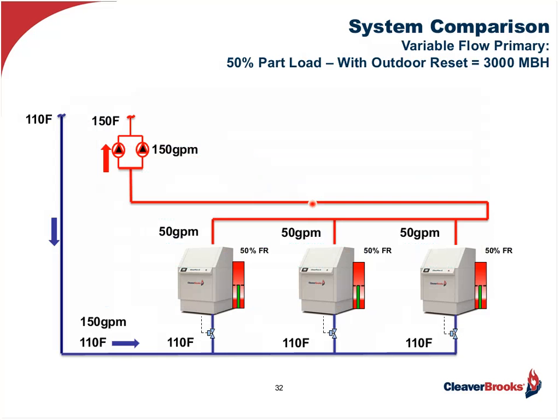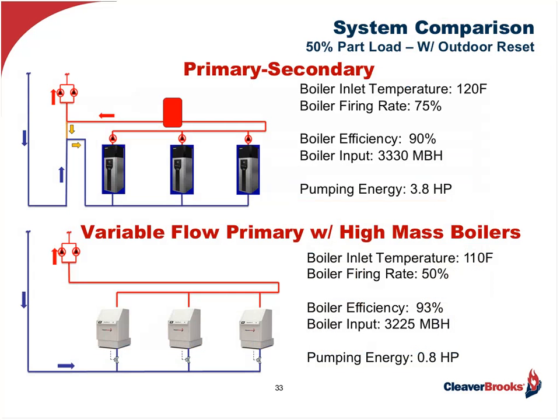So just looking at that again with the 110, and now the comparison. 75% firing rate with 120, 50% firing rate with 110. The efficiency, we've picked up about 3% on the boiler efficiency between the colder water and the lower firing rate. And of course, one of the biggest savings is we're picking up 3 horsepower because we're still running 2 boiler pumps at about 1.5 horses each. You don't have that penalty with the variable flow primary system.